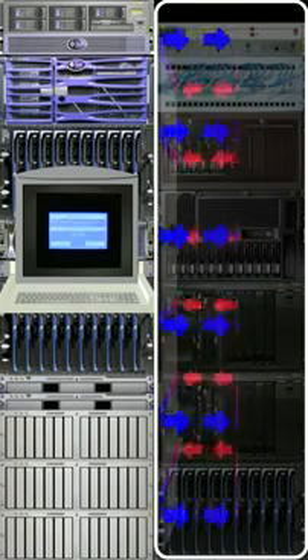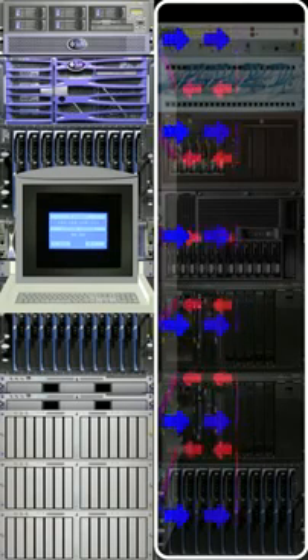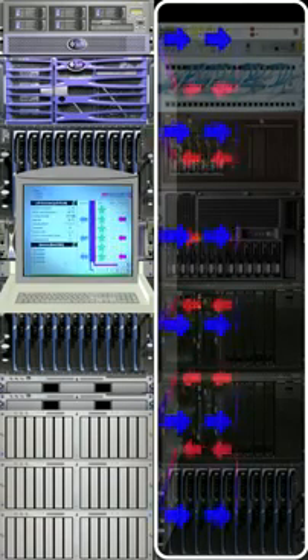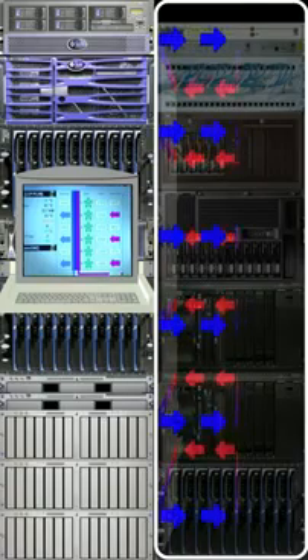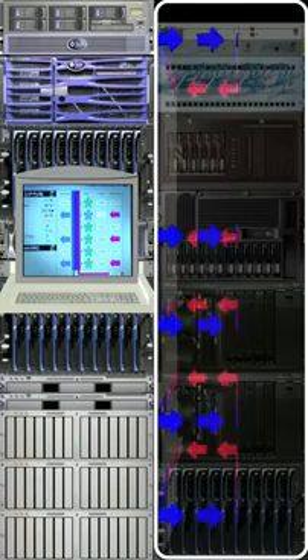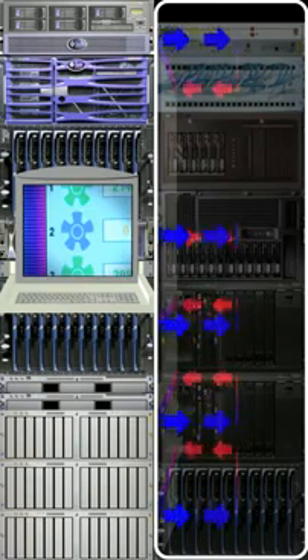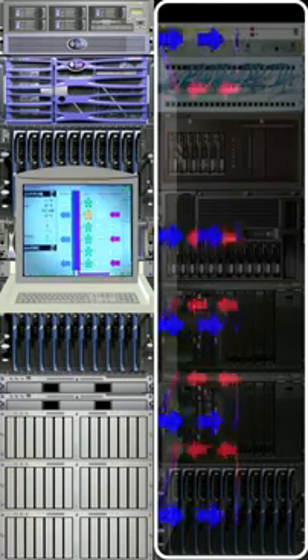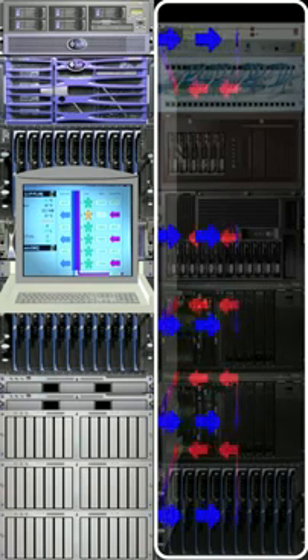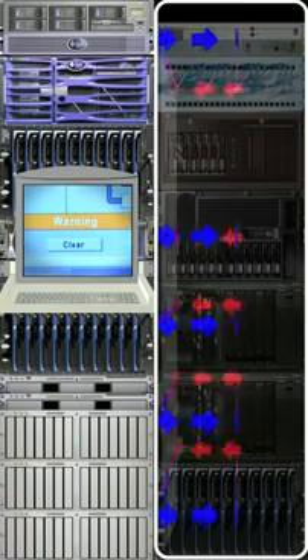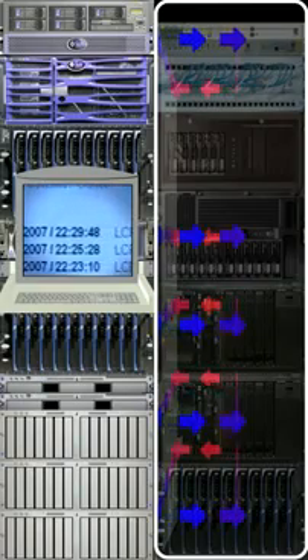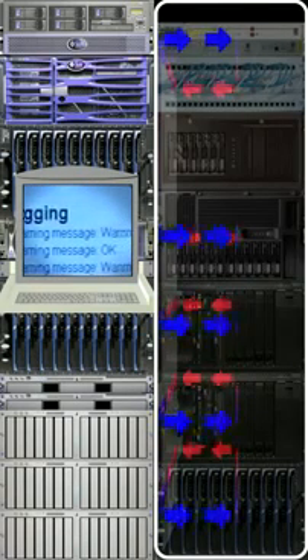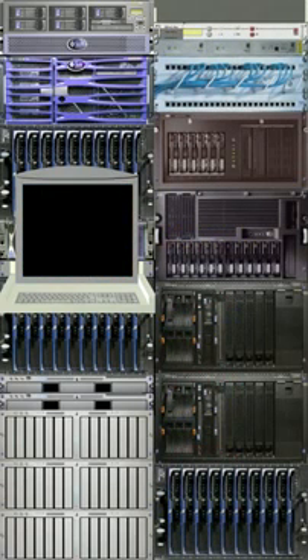The LCP Plus can be directly connected to your network, and via a web browser or an NMS, you can see a graphical status display. A mimic diagram shows the key elements of the LCP Plus and visually displays any fault. SNMP traps can be sent to network management software to alert remote users of any issues. Alarm logs are stored and are easily accessible via the web browser.